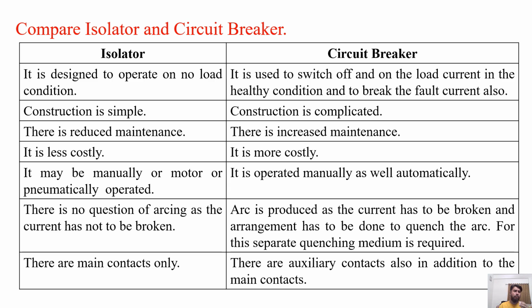So isolator is designed to operate on no load condition, whereas circuit breaker is used to switch off and switch on the load current in the healthy condition and to break the fault current also. So construction of the isolator is simple, whereas the construction of a circuit breaker is complicated. Isolator requires reduced or less maintenance, whereas in case of circuit breaker, maintenance is more as compared to isolator. Isolator is less costly, whereas circuit breaker is more costly. Isolator may be manually or motor or pneumatically operated, whereas circuit breaker is manually as well as automatically operated.